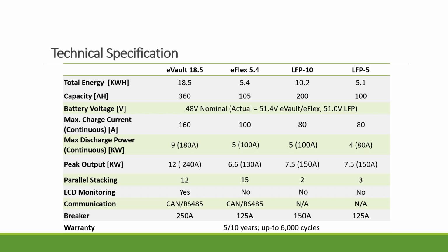The lithium battery has a battery management system, so it has maximum charging and discharging current, so you want to make sure when you select inverters that you operate within that parameter window. It also allows surge, because as you know, inverters these days can also provide surge, and it's especially critical during off-grid applications. So the BMS is also designed to accommodate the surge capacity that you need.